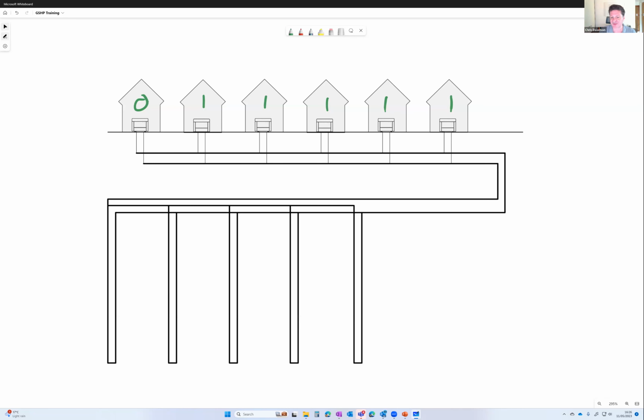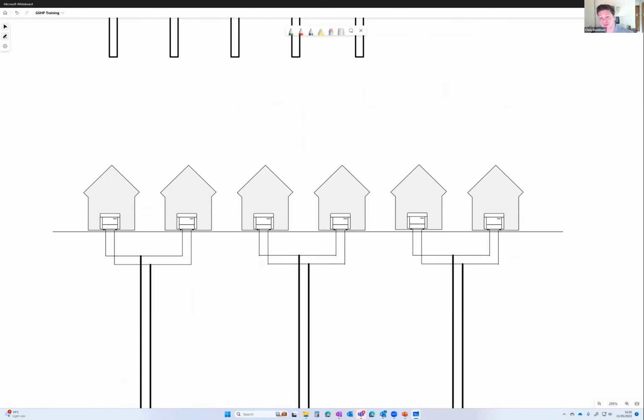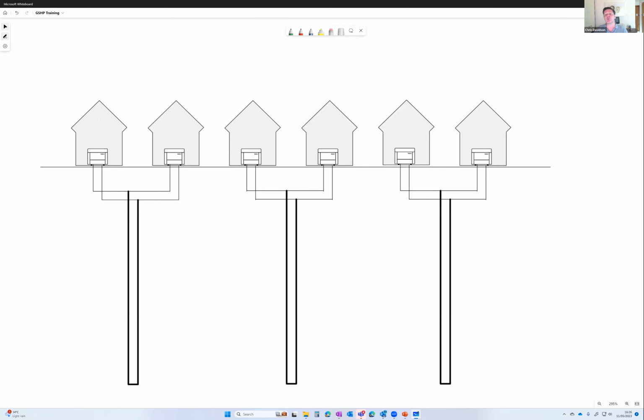The benefit of that diversity is we might save on boreholes, needing fewer overall. The downside is the pipework starts to get bigger, because it's got to deal with the flow rate of all the heat pumps - it needs to get bigger to keep the pressure drop down. If I've got time, I'll come back to pressure drop later in more detail, but in short, the more flow you've got, the bigger pipe you need. So an alternative, at the other extreme, would be to break that heat network up - I've shown it here with 2 dwellings per borehole.